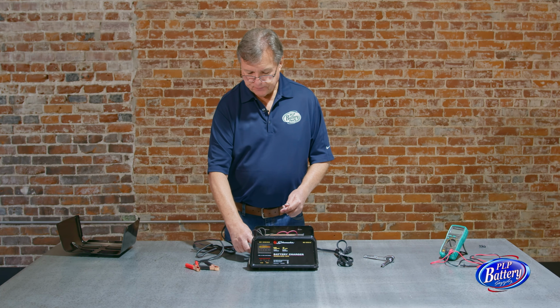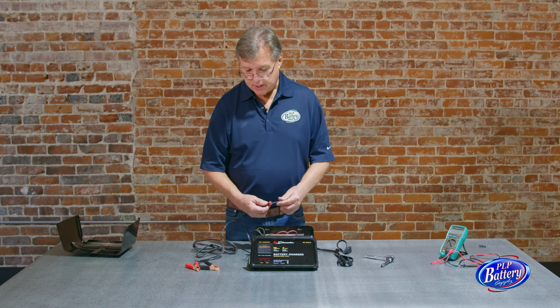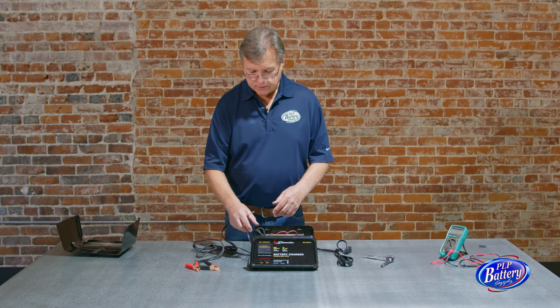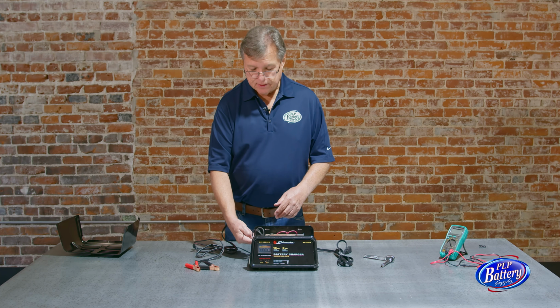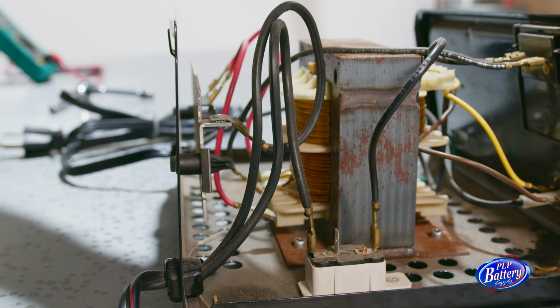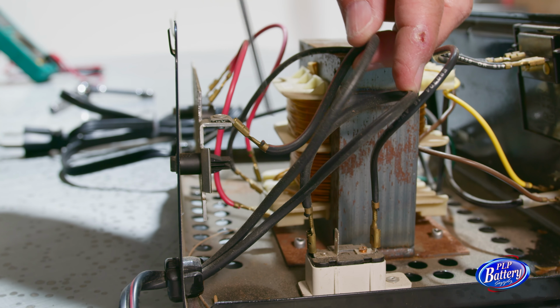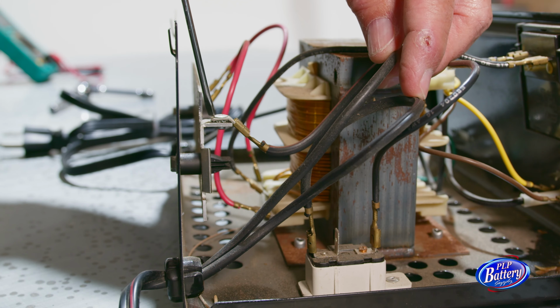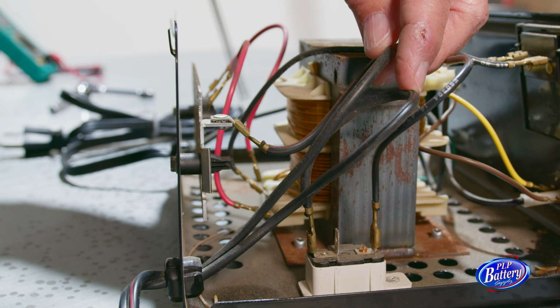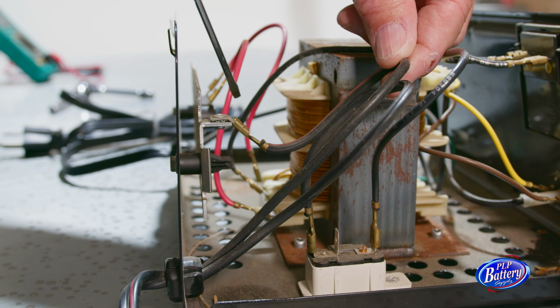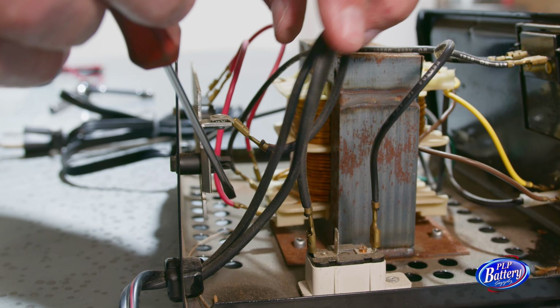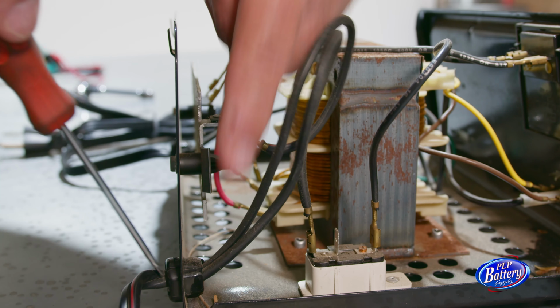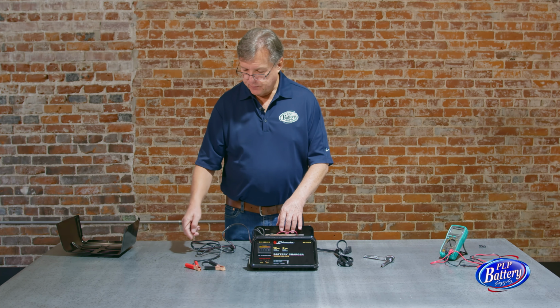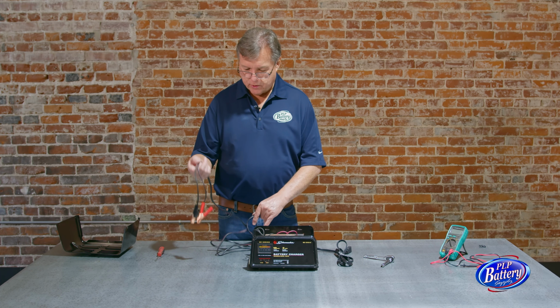If it's not, then you can replace that breaker. Again, not an expensive repair, not difficult. And then the last thing is the cable that runs, in this case, from the circuit breaker out to the clamps, and then its brother cable is also going out to the other clamp. It's the wire that's attached to the heat sink. This is the positive cable that's attached to the heat sink. That's why we're going to call this a positive output rectifier. But now you're down to checking this cord.